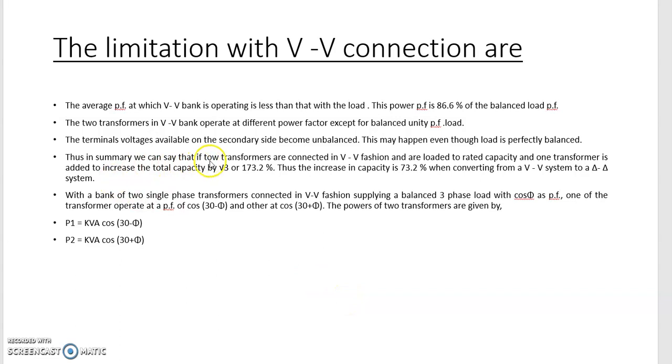Thus, in summary, we can say that if two transformers are connected in V-V fashion and are loaded to rated capacity, one transformer is added to increase the total capacity by root three times. Thus, increase in capacity is 73.2 percent when converting from V-V to delta-delta system.